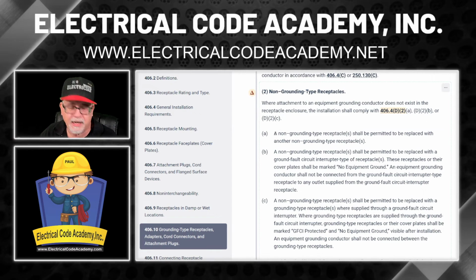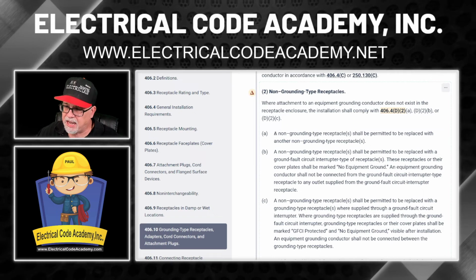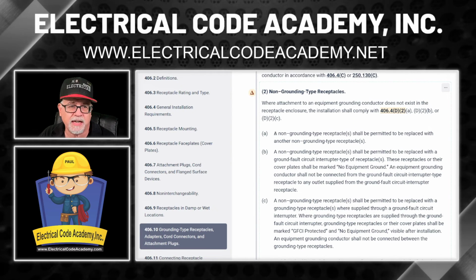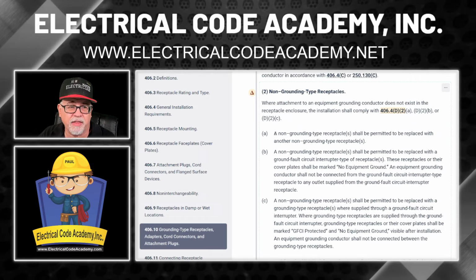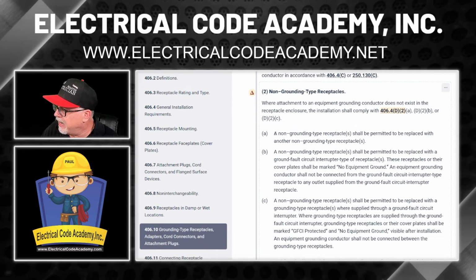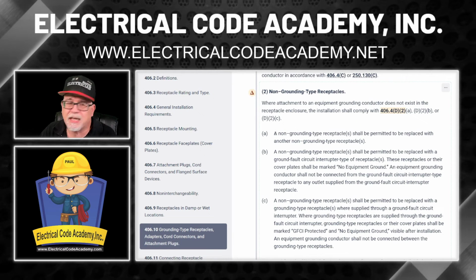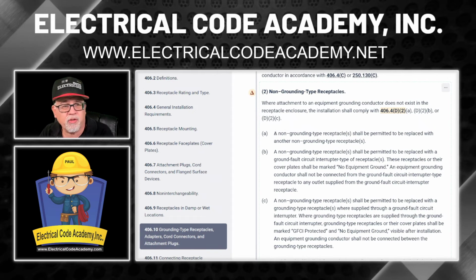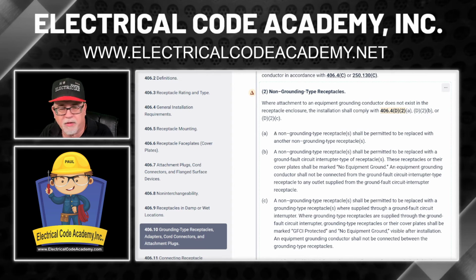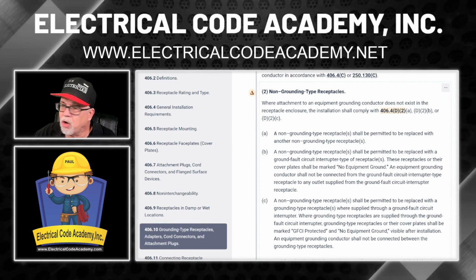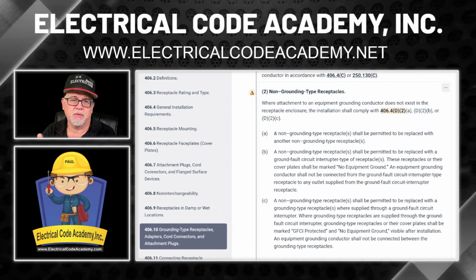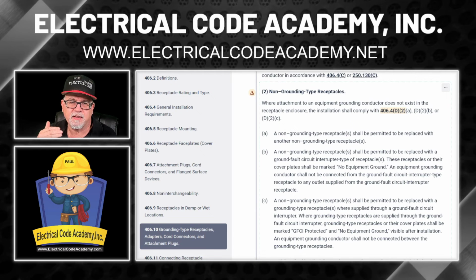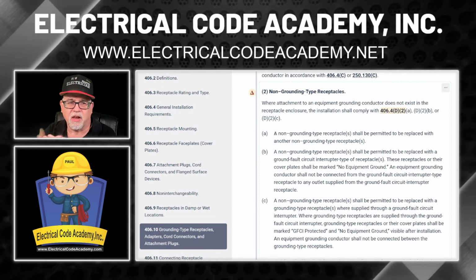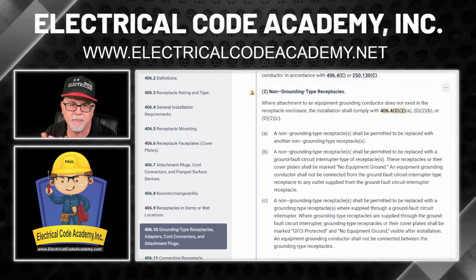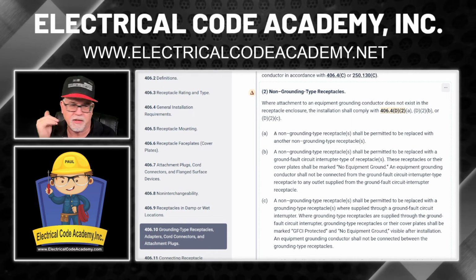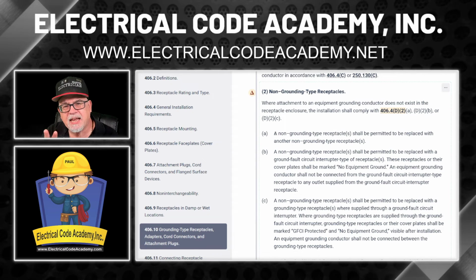Now, granted, you could rewire it and run brand new circuits and add equipment grounds, and you could follow some rules in 250.130 that would allow you to get an equipment ground there. But you're not doing that. At this point, you're like, okay, I want to give them some level of protection, but I also want to give them three prongs. So it's very convenient in a lot of the appliances and things that plug in today. So you go the route that he did. And if you look at the code, the first one, A, is 406.4D2A. That's just a like-for-like swap with a regular non-grounded type two-prong receptacle. Simple. Like-for-like. Okay?